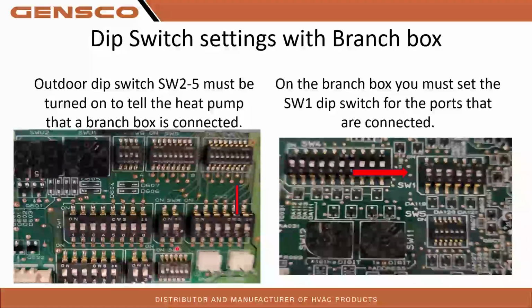Yes, just the address dials and your SW2. Yep. None of the other dip switches. Correct. A lot of these other dip switches are for model selections for heat pumps and stuff like that. Don't need to mess with those, but just this switch and your address dials, anytime you have a branch box, is going to be set up just like this. So this would be a good picture for you to take a screenshot of.